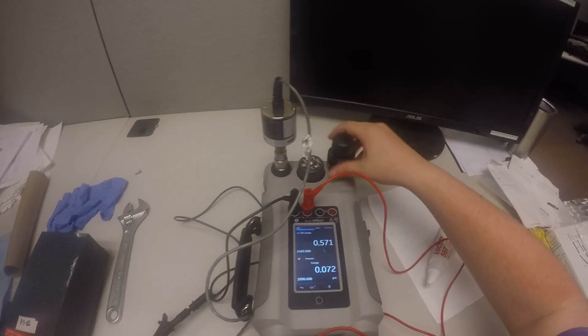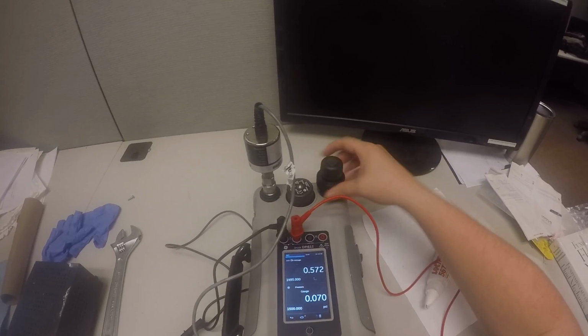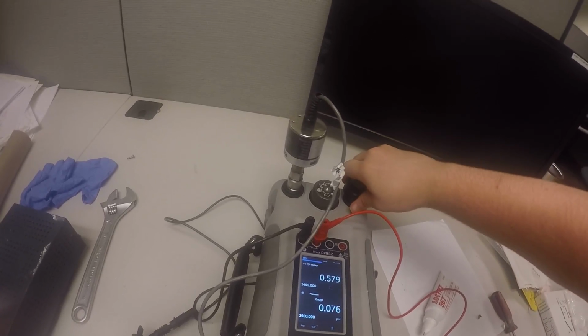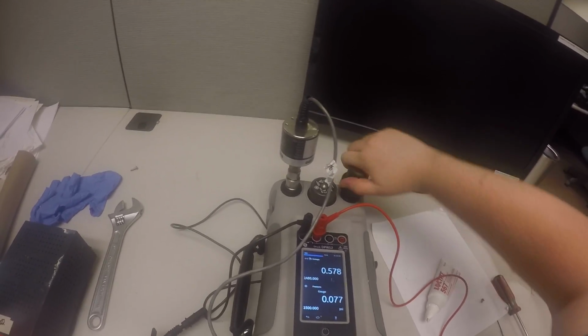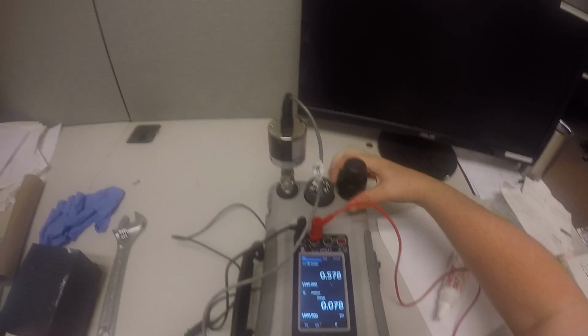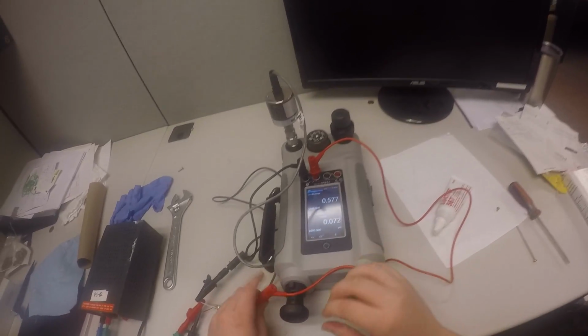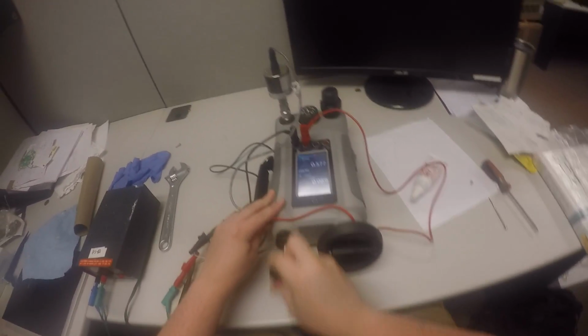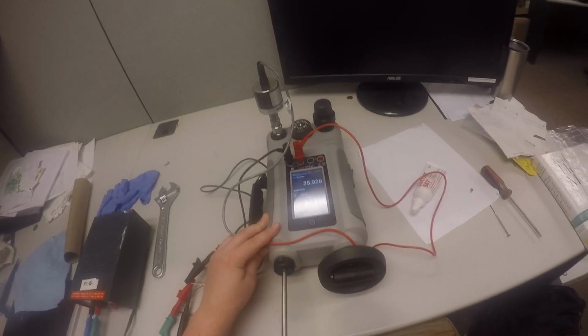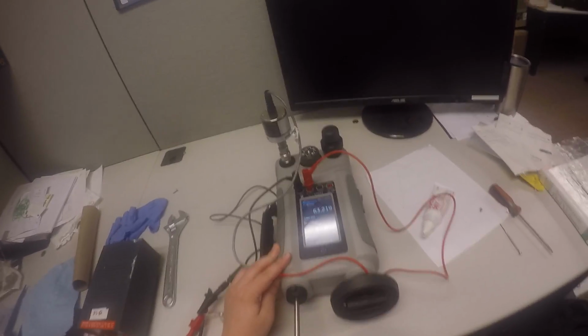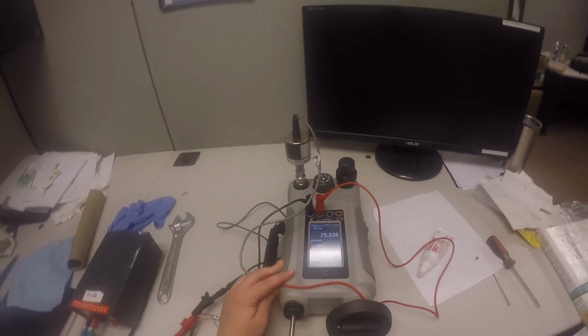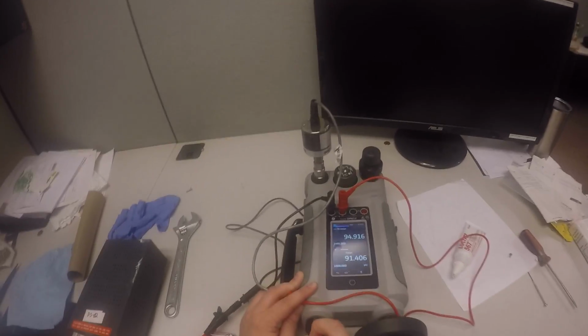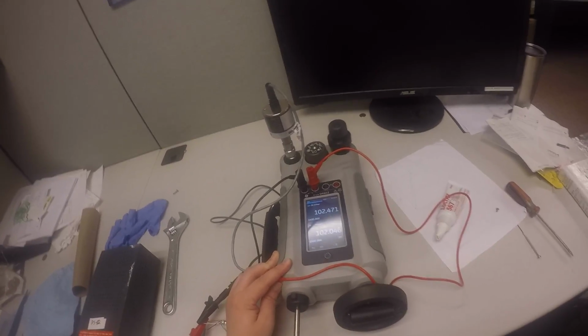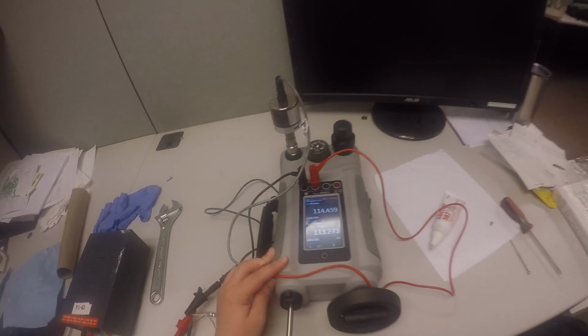And the next part is to close off the air exit on the Druck. And you just need to turn both these knobs on the right side. Now we can pressurize the Druck. So we're going to pressure up to under the maximum range of the pressure transducer. This pressure transducer goes up to 250 psi, so we're going to max out at 200 psi.